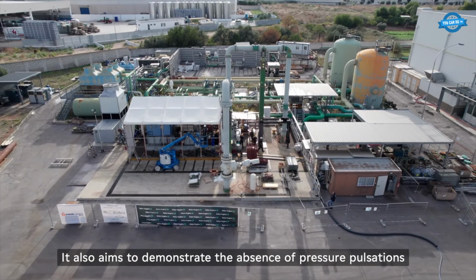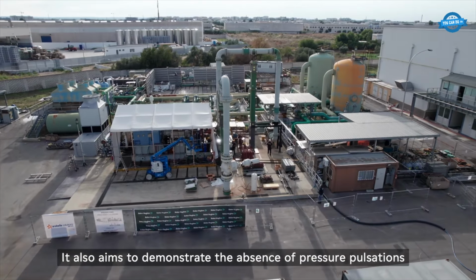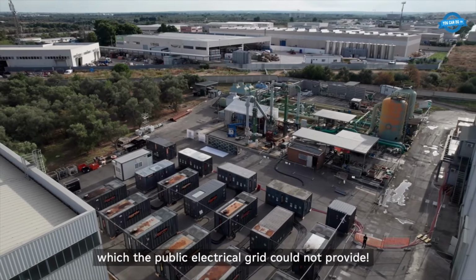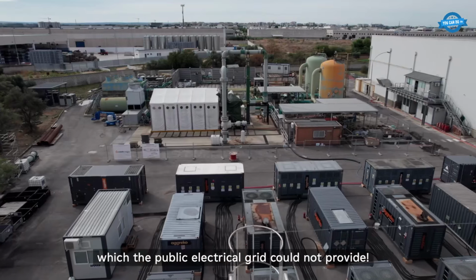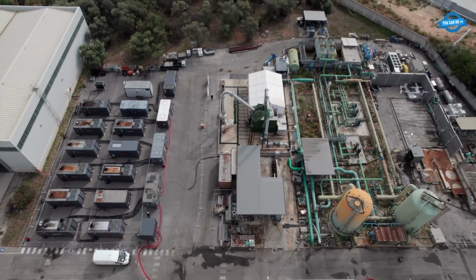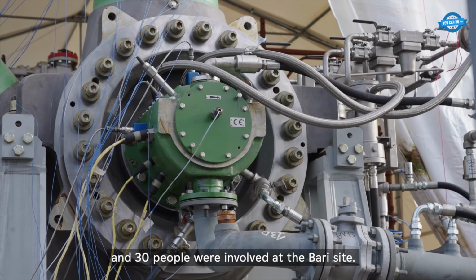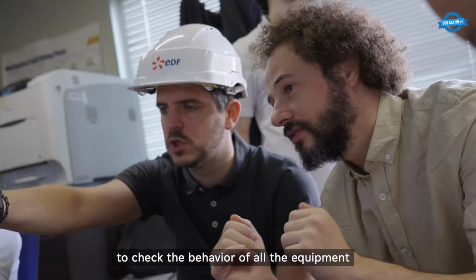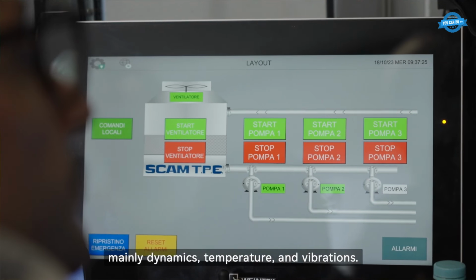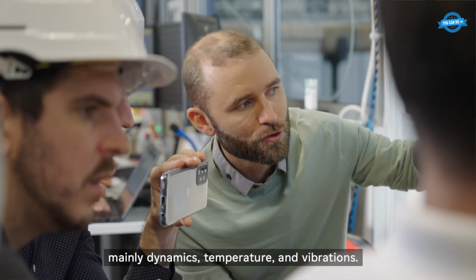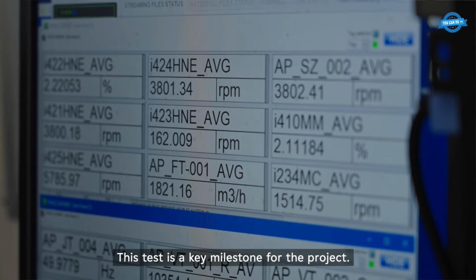Every rotating device on this scale gets tested before it ever touches the plant. A modern feedwater pump, 13 megawatts, 90 bar discharge, 15 meters long, 110 tons, has to prove it can run at full load without vibration pulses that would crack downstream piping.